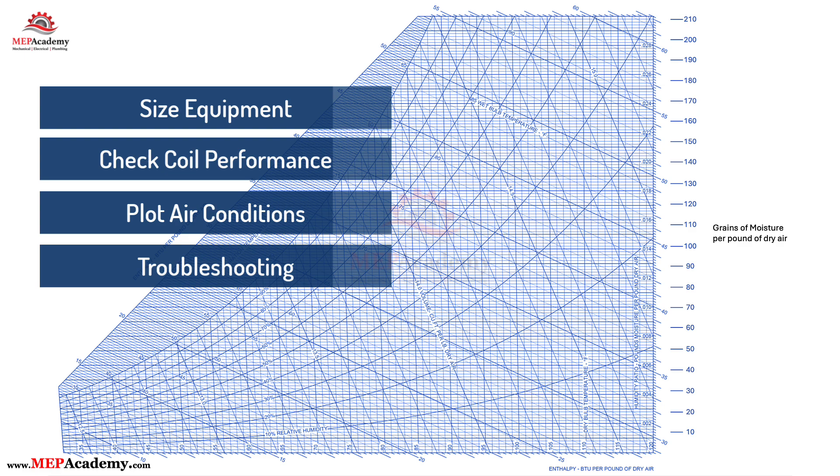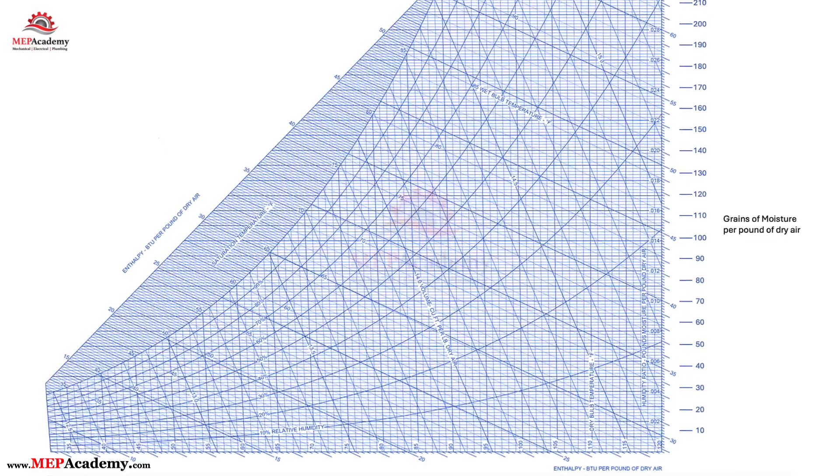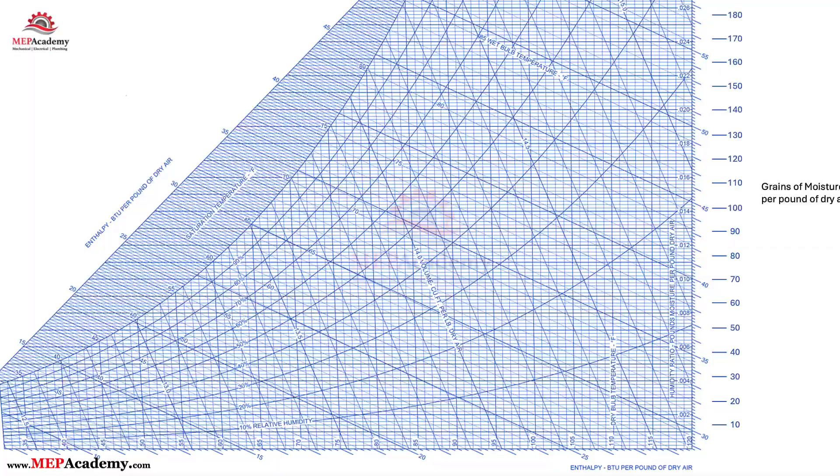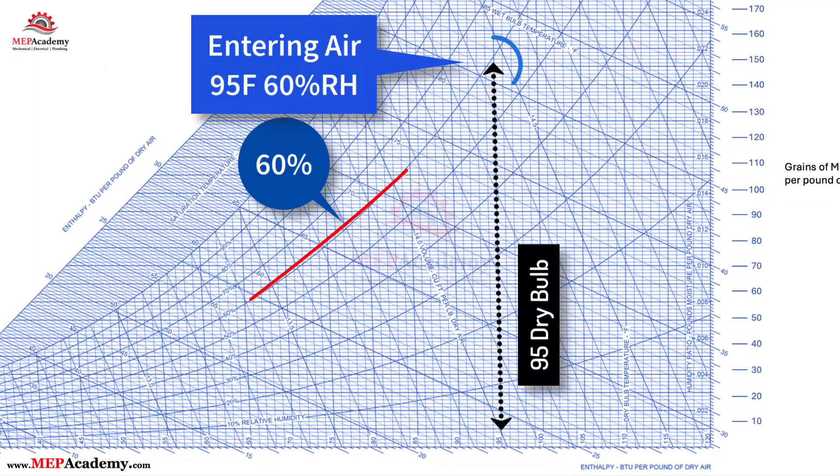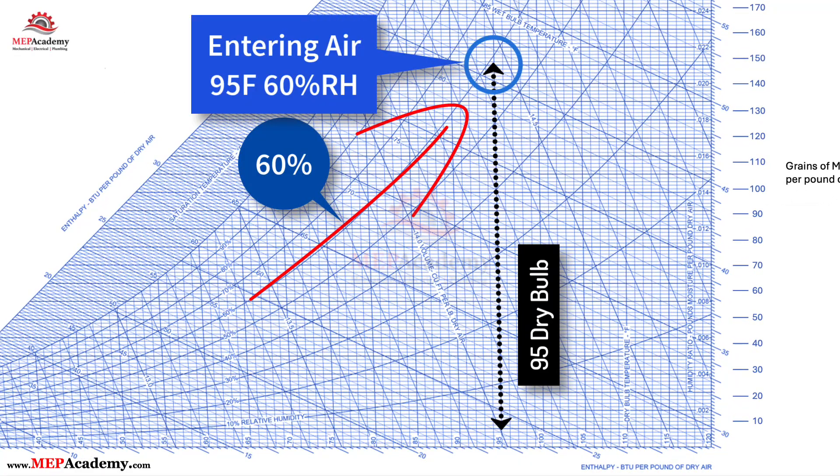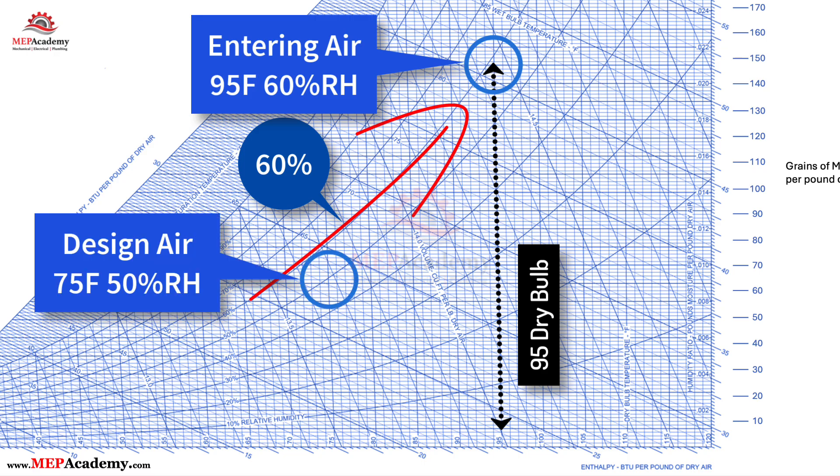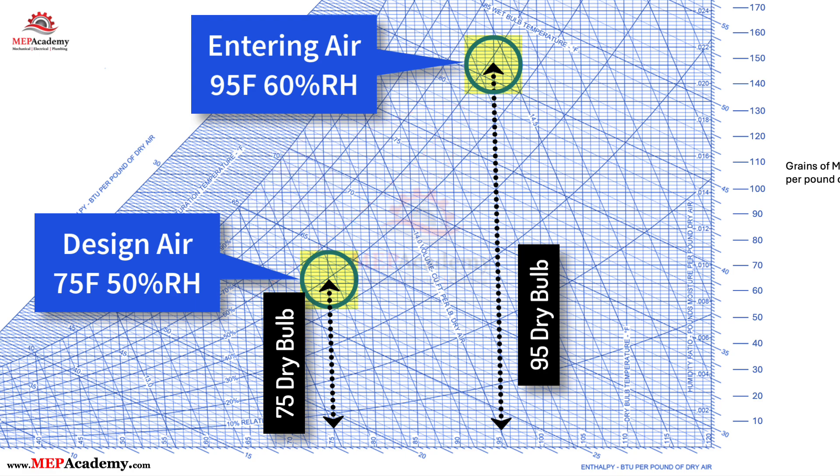Let's walk through a simple HVAC scenario. Problem: You're conditioning air in a commercial office building. Outdoor air is coming in at 95 degrees Fahrenheit dry bulb and 60% relative humidity. You need to condition it to a comfortable indoor design condition of 75 degrees Fahrenheit dry bulb and 50% relative humidity. Step 1: Plot the outdoor air. This is your starting point. Use the dry bulb and move up to the 60% relative humidity curve to find the outdoor air condition.